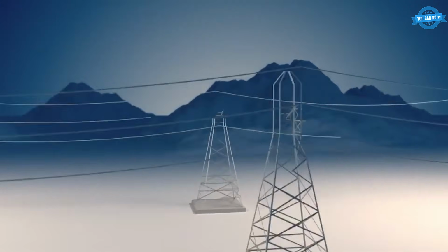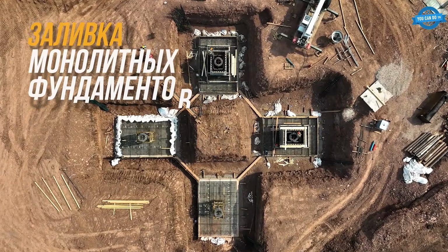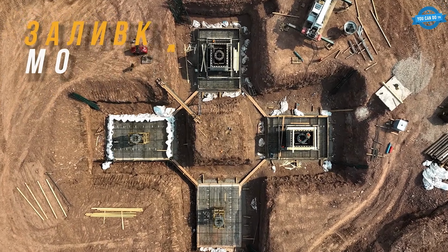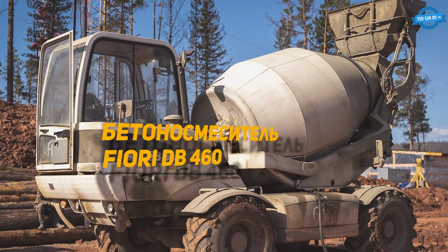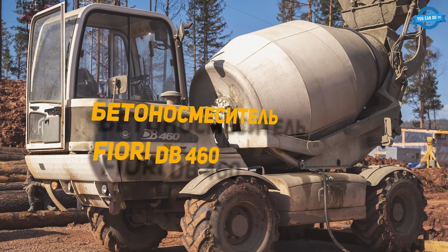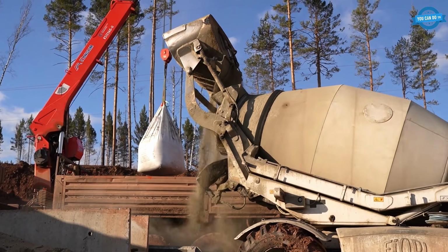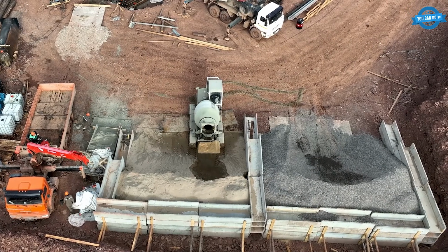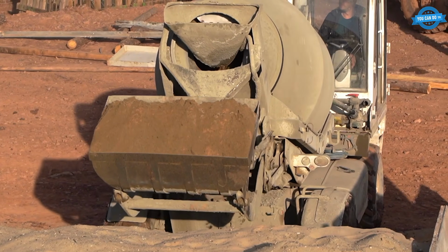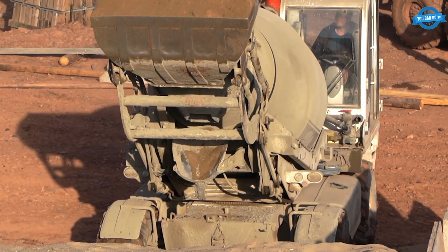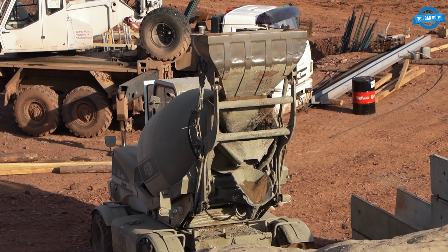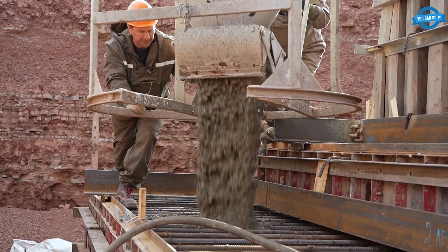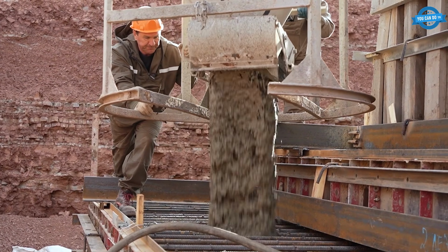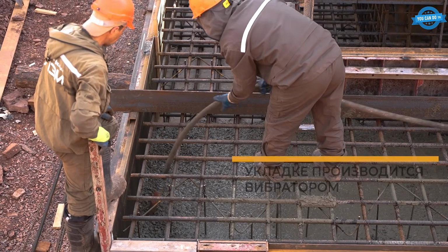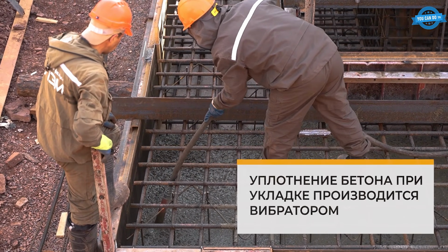The cable lines that move electricity across continents need something even more solid than the towers, a concrete foundation that holds the tower against decades of wind, ice, and conductor tension. Pour one wrong and the whole line goes down. Each monolithic foundation for a 500 kilovolt river crossing tower takes 54 cubic meters of B30 F400 W8 concrete, poured continuously in 3 tiers, bottom, middle, top, over 20 to 24 hours without stopping, even through the night.